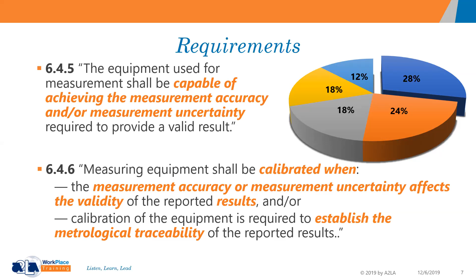This report does not include those that are cited to A2LA's policy on traceability, the P102 document, but only those that were cited against this particular clause. So there are a lot more tied around with traceability that are not included in this assessment here. But the one thing I do want to make sure that you're aware of is that if you're not required to establish metrological traceability in that measurement for that particular device, then does it need to be calibrated? And that's the critical question that you need to take into consideration. And that will tie in very nicely when we talk about verification of equipment in section 7.7.1 a little bit later.